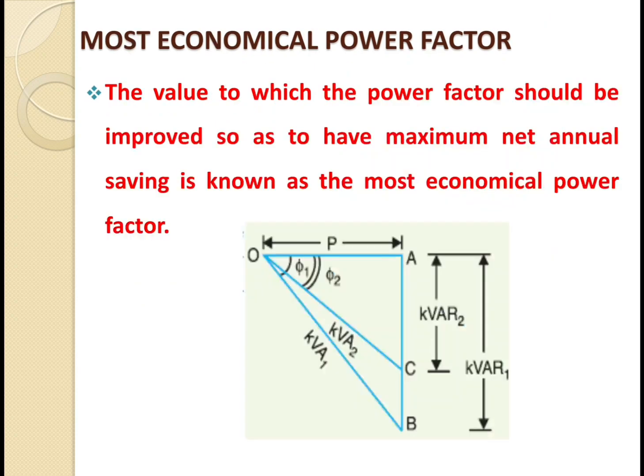Now we will go for the Most Economical Power Factor. The value to which the power factor should be improved so as to have maximum net annual saving is known as the Most Economical Power Factor. If a consumer improves the power factor, there is a reduction in maximum KVA demand, and hence an annual saving over the maximum demand charges. By improving the power factor, the maximum demand at the consumer side decreases, resulting in annual savings in maximum demand charges.